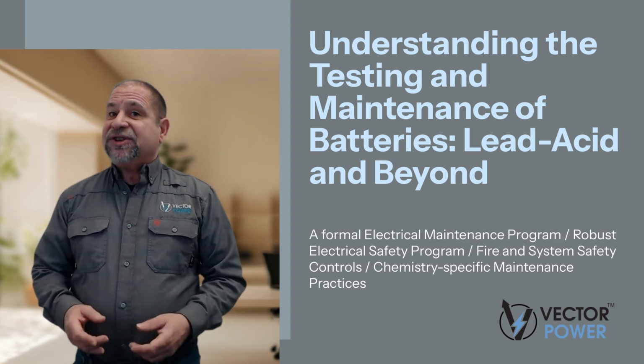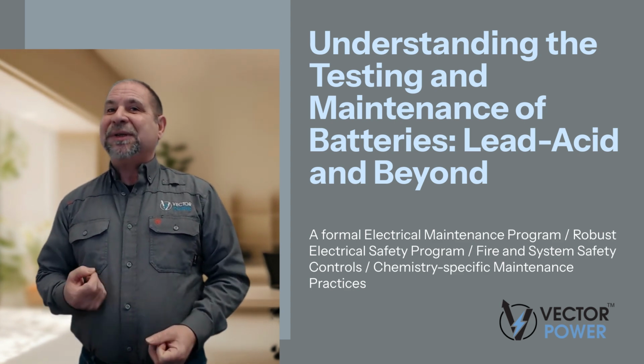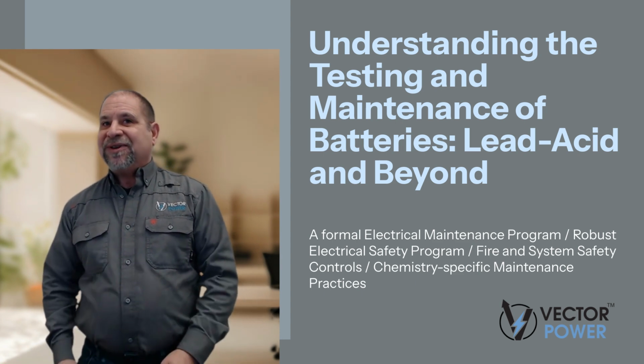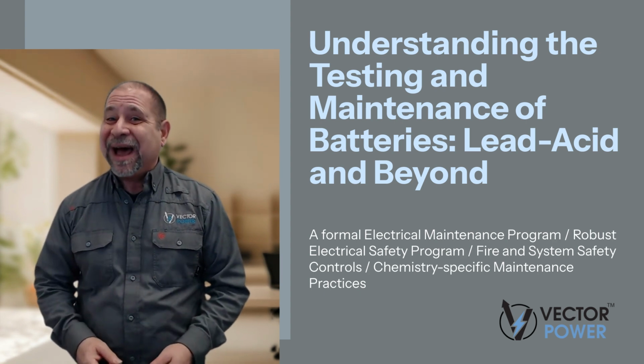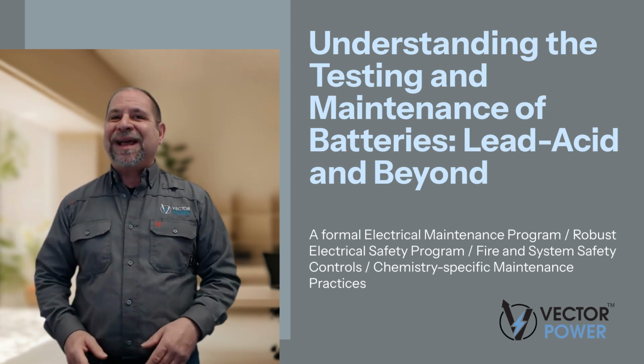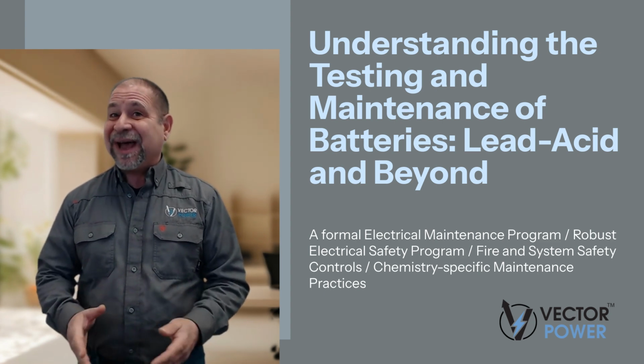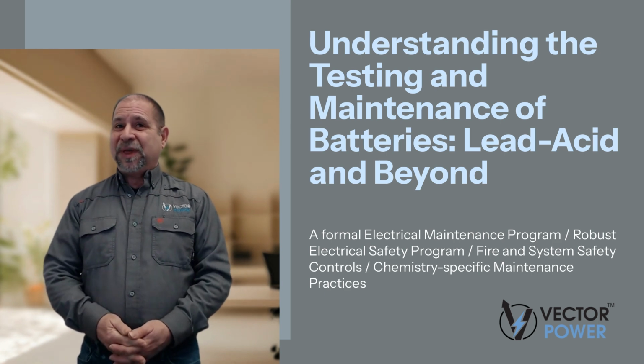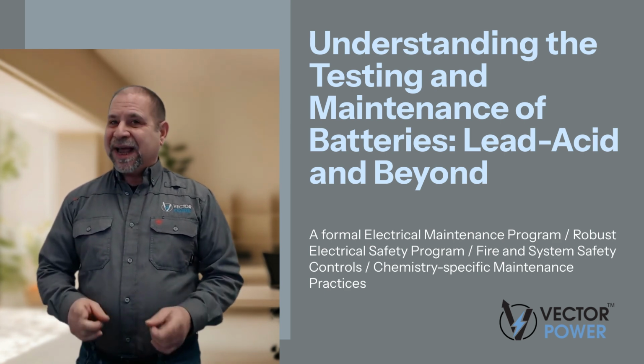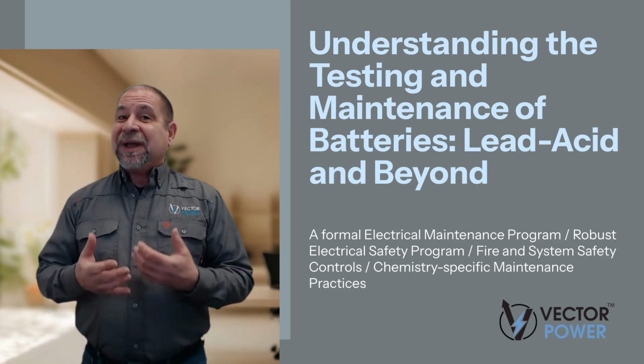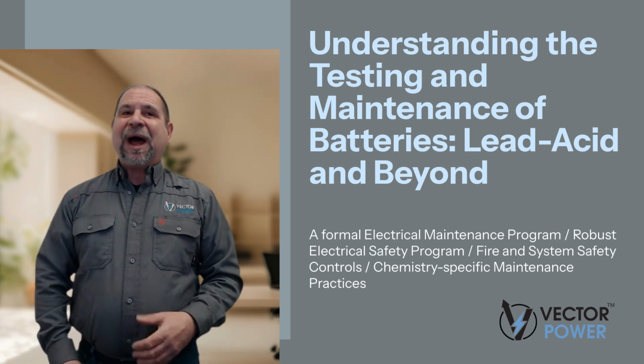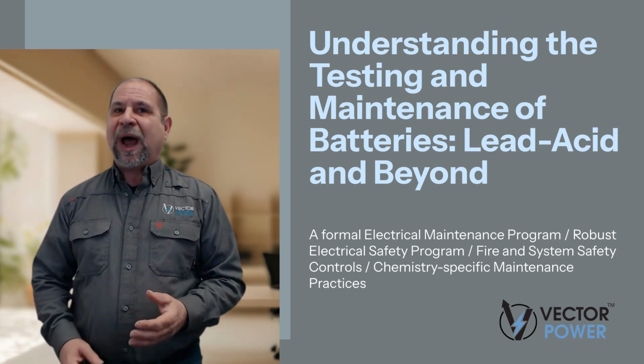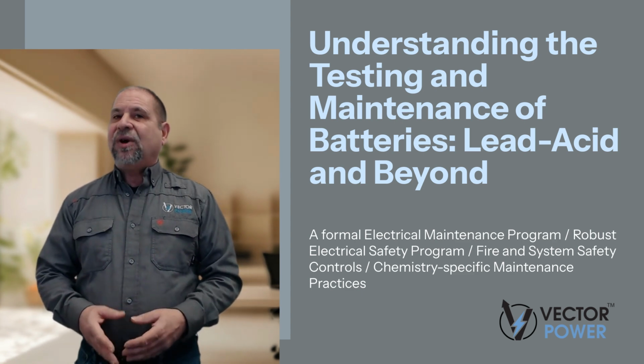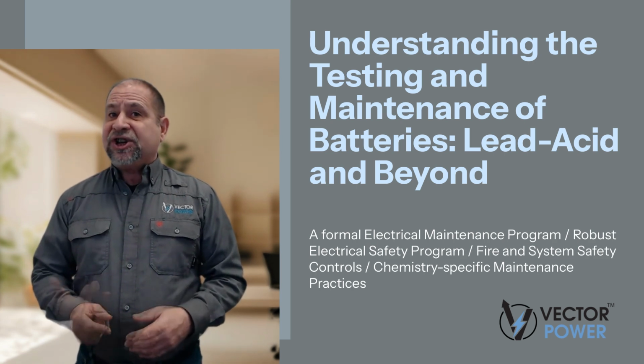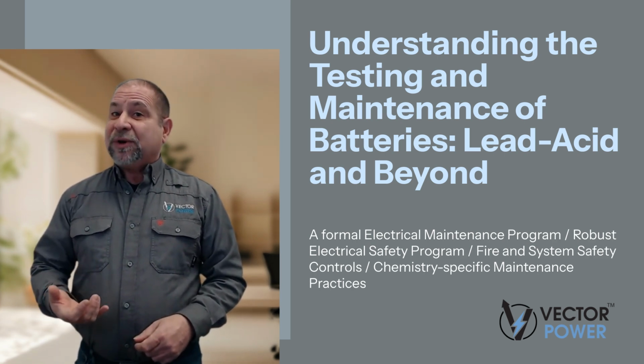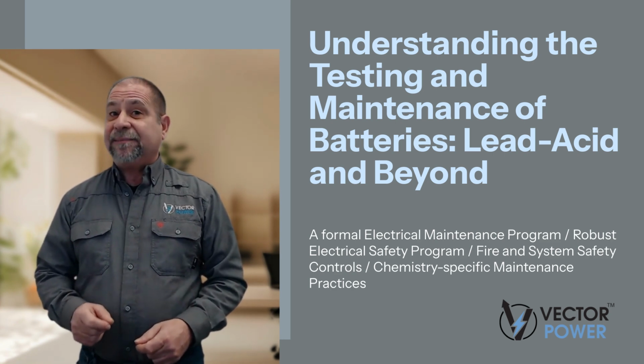A robust program for stationary batteries and energy storage systems is built around four mutually reinforcing pillars: a formal electrical maintenance program, EMP, as required by NFPA 70B, using predetermined, condition based, and predictive techniques with strong documentation and periodic audits. A robust electrical safety program aligned with NFPA 70E, covering risk assessments, arc flash and shock protection boundaries, energized work controls, PPE, and training.